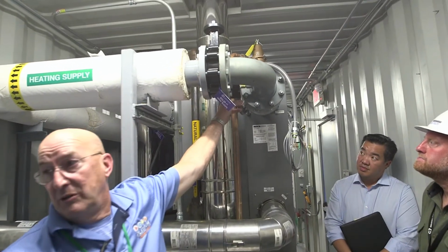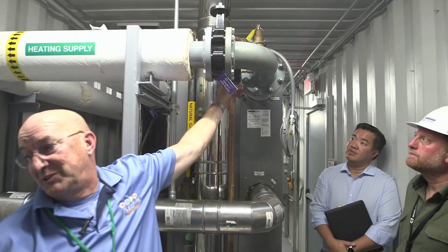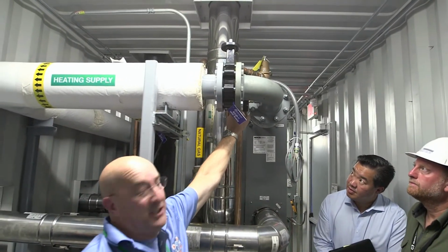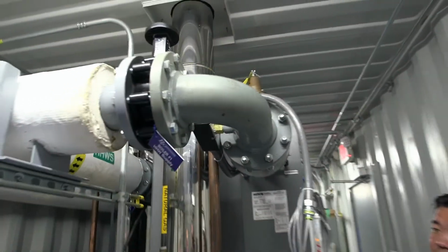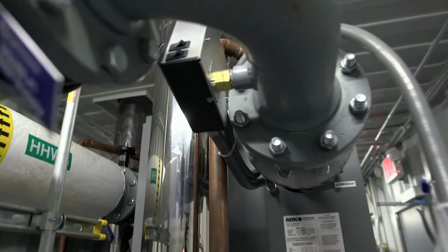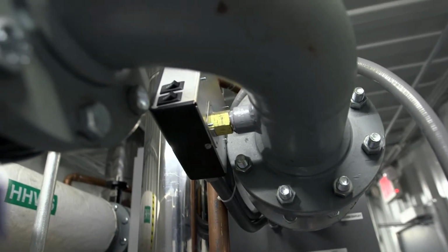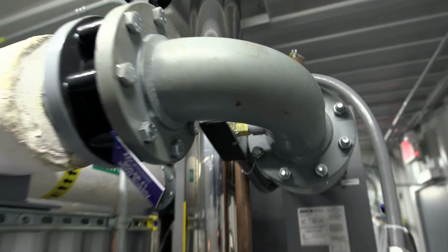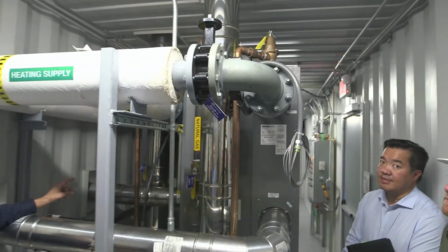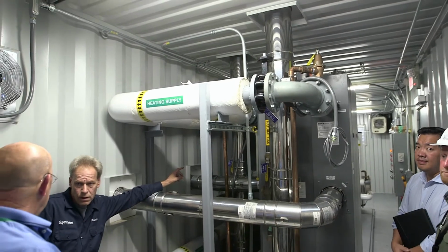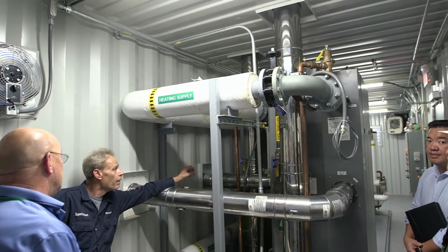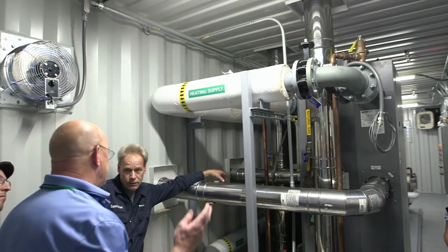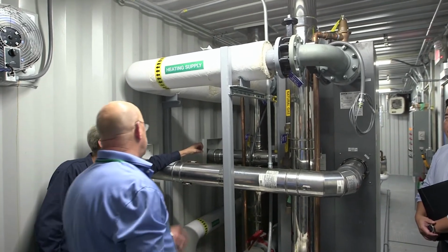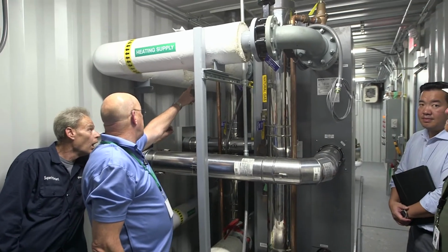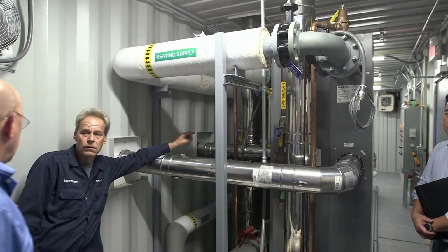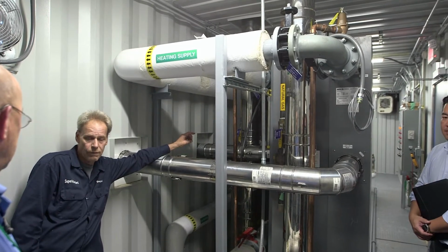This is your secondary low water cutoff right here. I know it's a little difficult to see. All right? But there are two buttons on it. The button to the left is a test button, just like that one there. To say you were wondering if it worked, you were curious, you could press and hold the test button, and it'll set it off on low water. Okay. Then you can hit the reset button. Okay? Once you hit the reset button, she's back in the cycle. And you'll know it's off on reset because there's a red light on top that'll be lit. It tells you it's off on low water and it's not going to come back on until it's reset. Okay?